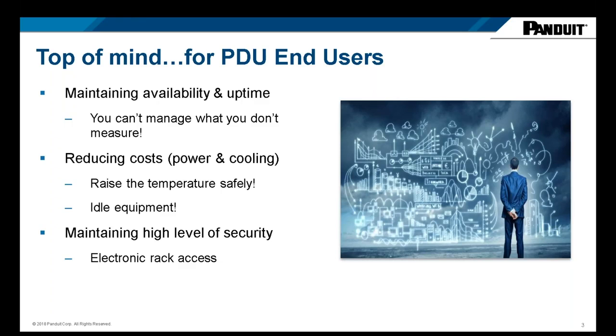Of course, the number one cost for a data center operator is cooling - the cooling costs are even above the power consumption costs, which are of course a lot. So one of the things top of mind for this customer segment is they want to reduce costs by raising the temperature in the hot aisle or in the back of the cabinet safely. You don't want to give up uptime, but you do want to reduce costs.